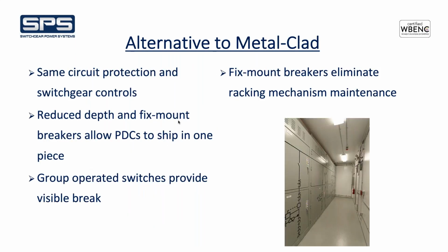So the second alternative, a place to apply this concept, is as an alternative to metal clad switchgear. You get the same circuit protection and switchgear controls that maintenance personnel used to metal clad switchgear are used to. It is reduced depth and the fixed mount circuit breaker. So if you're specifying the gear to be in a PDC building, the depth of the switchgear is reduced, and the circuit breakers being fixed mount allow you to shrink the width of the aisle, which brings the total building width down to a point where we can ship it in one piece and avoid shipping splits and reconnecting at site.